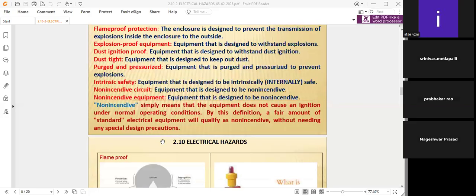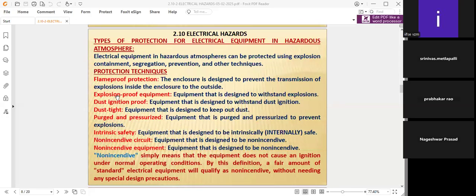The dust technique we will be discussing here is very important. Explosion proof, you already know: equipment that is designed to withstand explosions. Dust ignition proof is equipment designed to withstand dust ignition, because these all come under Class 1, Class 2, Class 3 hazards, and Zone 0, Zone 1, Zone 2 hazard classifications are also there. That's why we'll be discussing all these things.